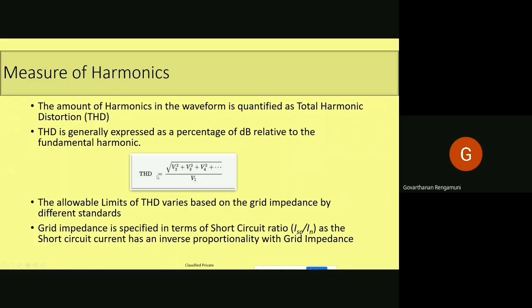If the total harmonic distortion is increasing, then you are injecting more harmonics into the grid. This needs to be understood. The allowable limits of THD vary by different standards based on the grid impedance. Grid impedance is always specified in terms of short circuit ratio. You will not see the grid impedance specified in the standard, but they will specify the short circuit ratio, because the short circuit ratio indirectly refers to the grid impedance, since short circuit current is inversely proportional to the grid impedance for the given voltage.